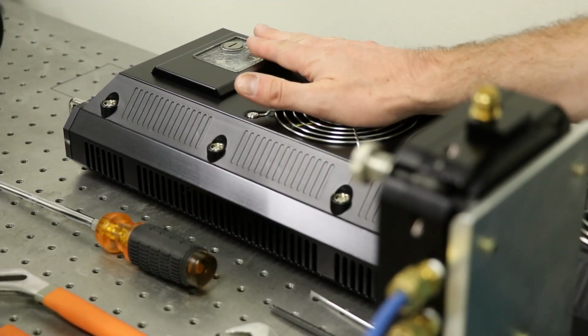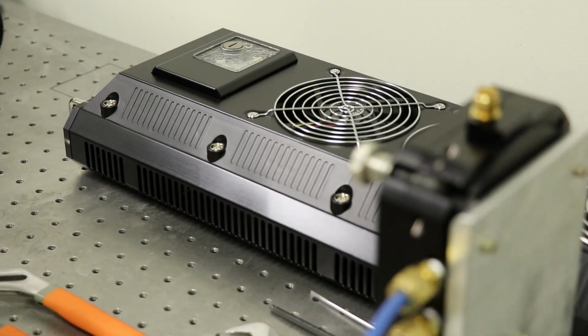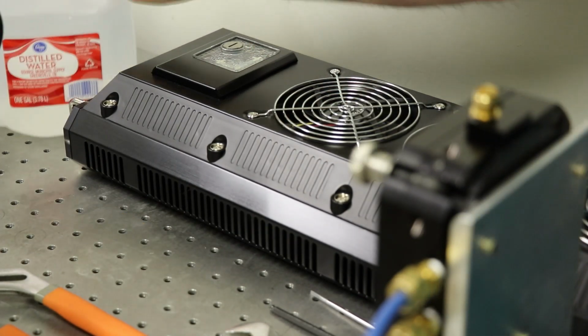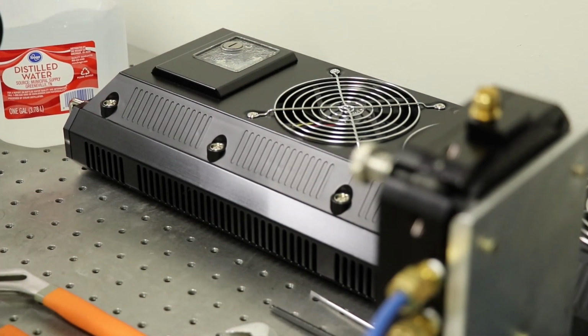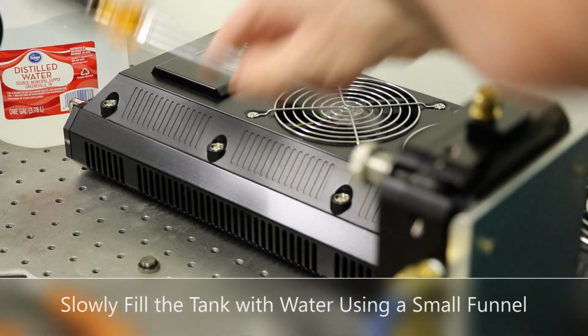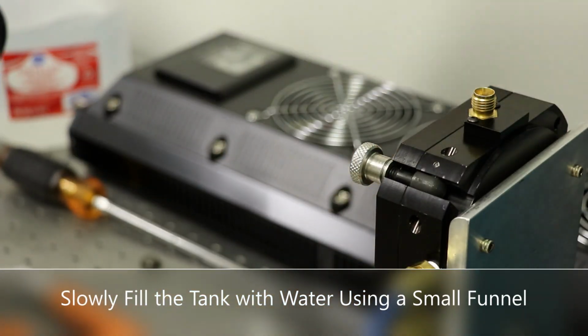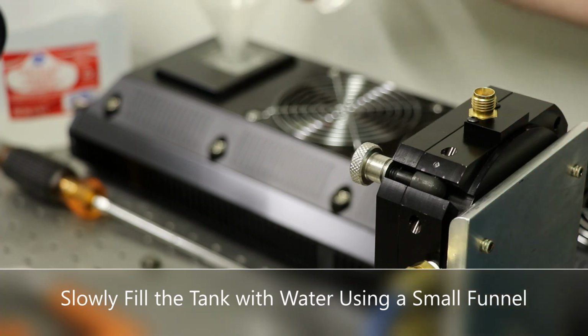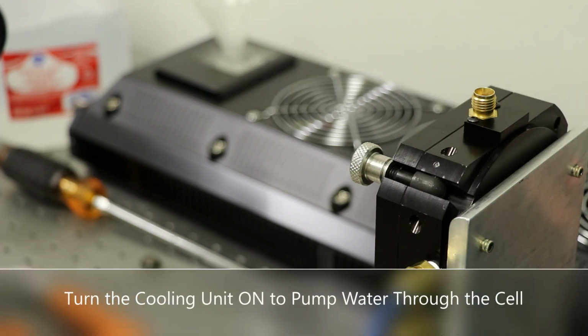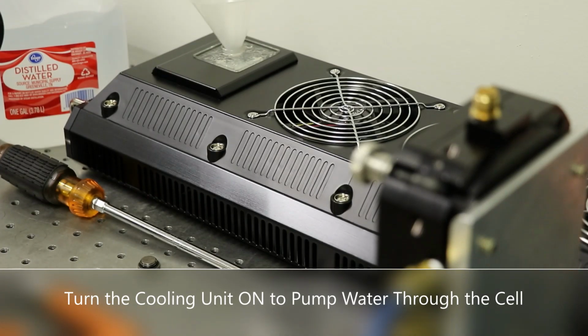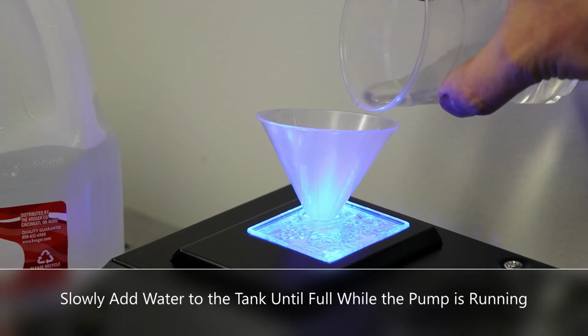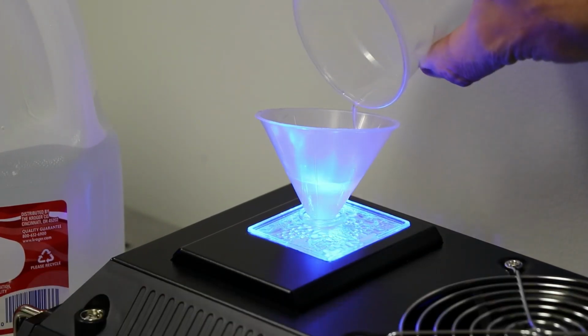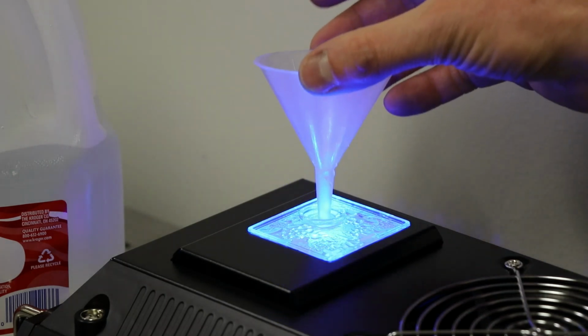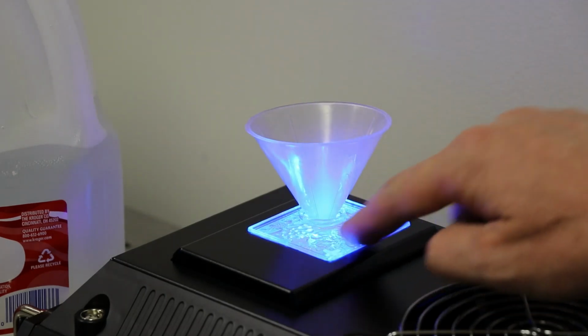Next, we need to make sure we have enough water in our cooling system. For this, only use distilled water. That will prevent buildup in the lines. Use a small funnel and slowly fill the tank. With the unit connected to the calibration cell, turn it on and check that there is enough water in the system. This will pump water throughout the entire system. Fill this until the water level inside the tank reaches just below the top.